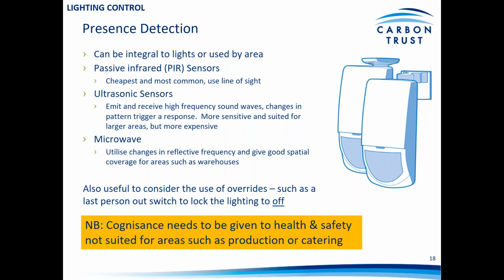And as well as looking at these sensor controls, overrides are beneficial too, such as the last person out switch that we mentioned, which can switch off the system and avoid it being triggered unnecessarily when the building's unoccupied. They wouldn't apply to all areas, and consideration needs to be given to the likes of production spaces or catering spaces, or areas where a switch off in the lighting would cause difficulties. If somebody's operating a machine, or if they're cooking or things of that nature, you want to make sure that the lighting's kept on continually in those areas.